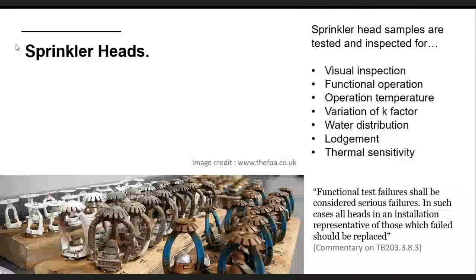The heads that you've taken out will obviously need to be replaced. You can replace them from the spares kit, but often you're not going to have enough heads in the spares kit, so you would have to replace them with new heads, generally speaking. Obviously, if the same heads are still available to purchase, then ideal. You can put in an exact like-for-like replacement, but often you'll find after 25 years the heads are just not going to be available. Definitely the heads pictured in the foreground there won't be available anymore. So you'd have to choose some of similar performance and replace them with those.